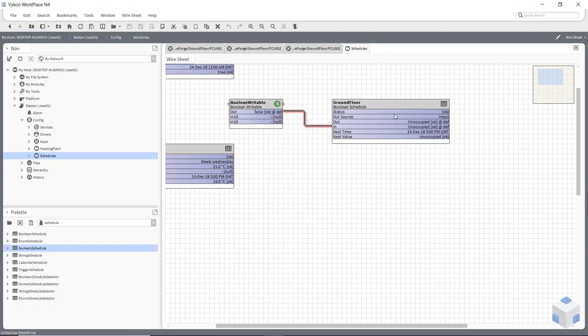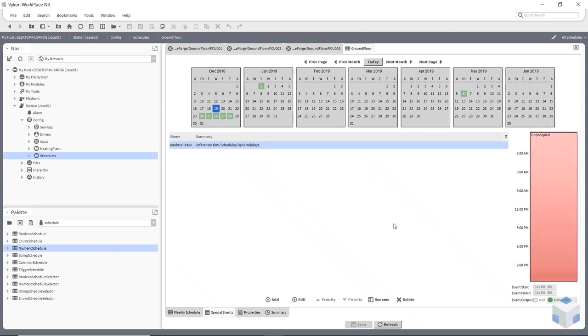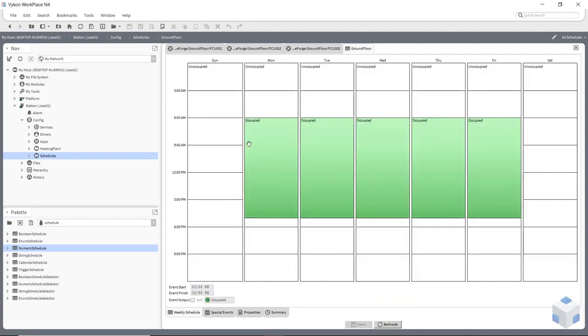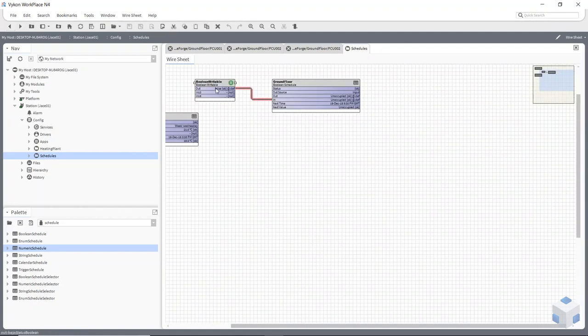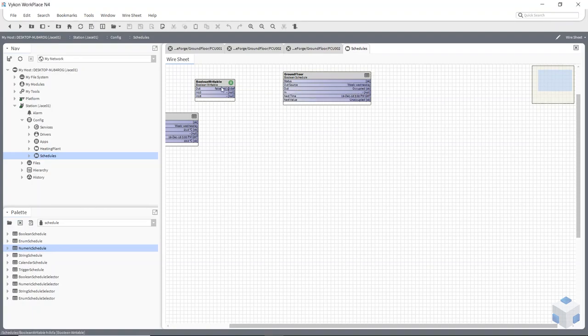So it's now using this to control what this component's doing. So this in slot is actually taking precedence or priority over everything inside it. So even this bank holiday will now be overridden, and also all these time schedules will be overridden as well. So this is priority number one. So if you had something linking, I don't know, like a time extension or something like that, it would override what is happening inside that component. So that's priority number one. So now I've released it. It's gone back to the normal weekday schedule. So now it's using this weekday Wednesday.